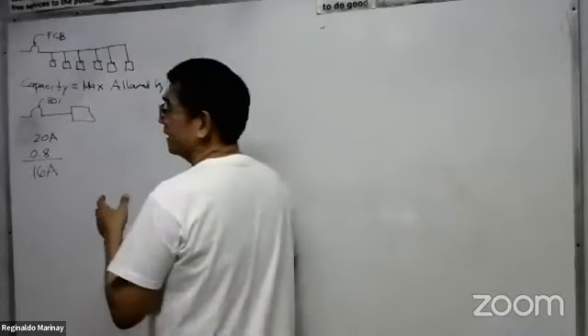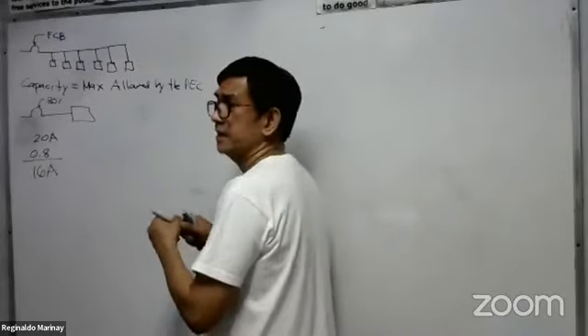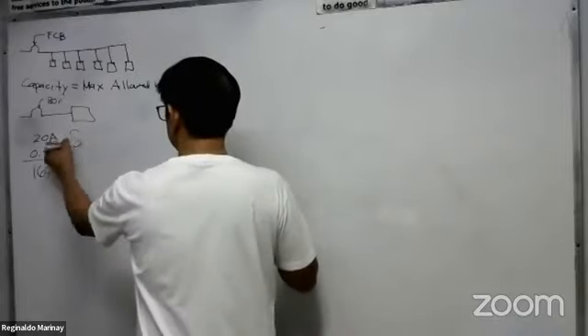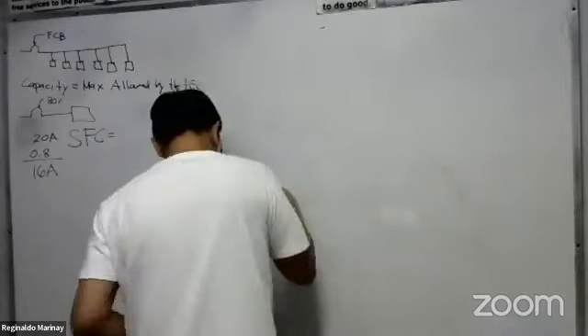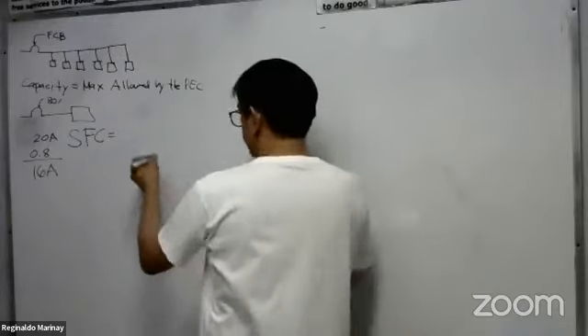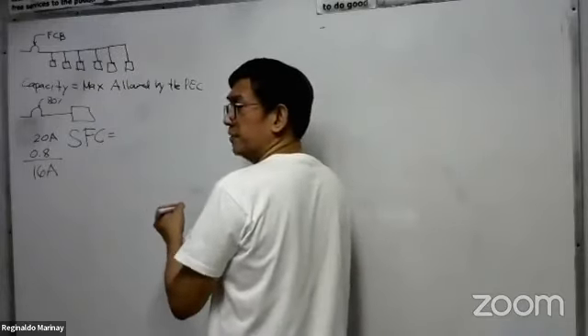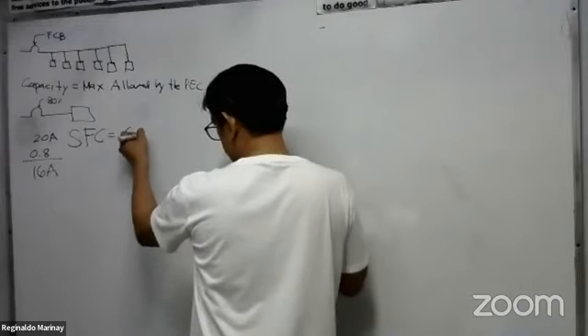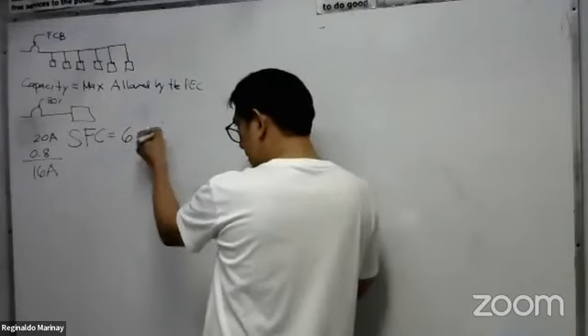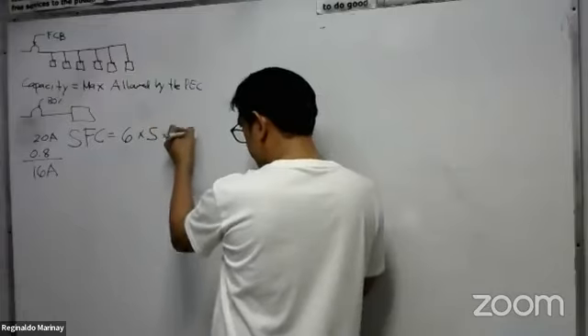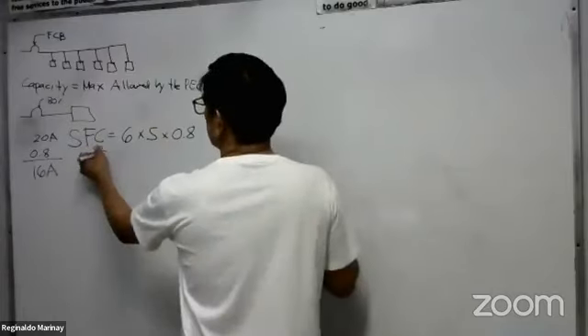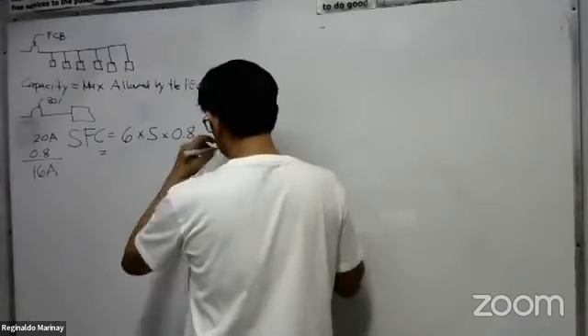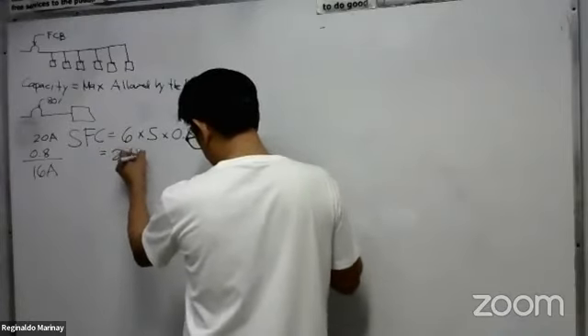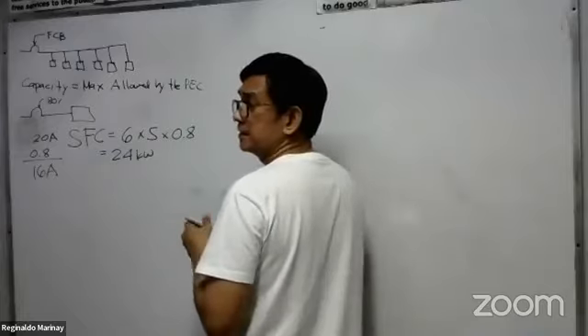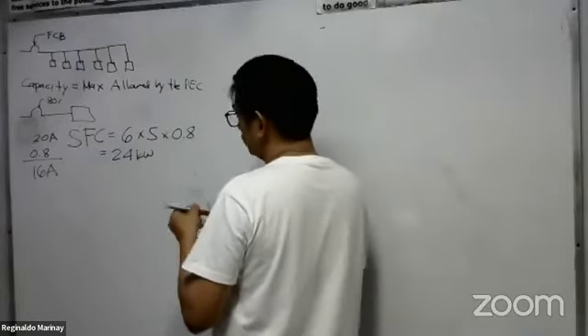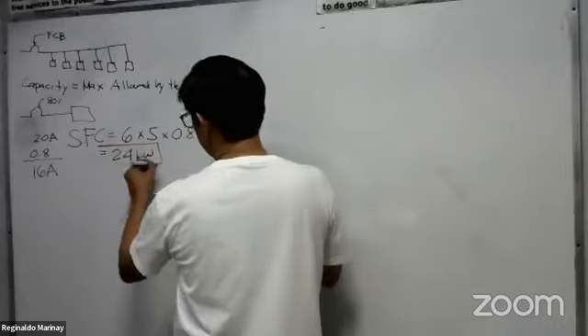6, okay, let us get now the service feeder capacity. Let us call this the service feeder capacity. So, we have here 80%, no? Or shall we say, we have 6 times the 5 kilowatt, and then let us multiply it by 0.8. So 6 times 5 is 30, times 0.8, so 24 kilowatts. That is the maximum allowed by the code.